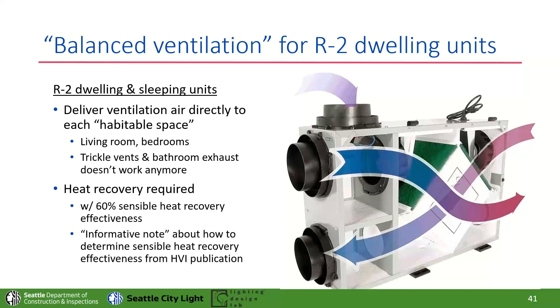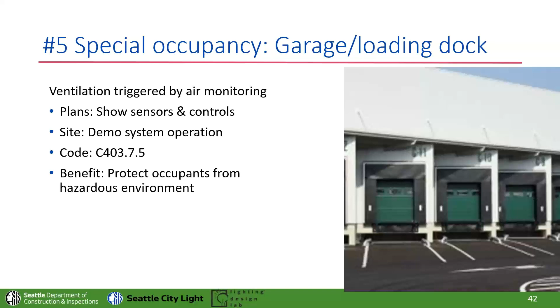Loading docks are another tricky one. Ventilation ramps up when there are contaminants in the air, so your plans have to show those sensors and controls are working, and someone on site has to be able to demonstrate that it's actually turning up the ventilation when there's stuff in the air.